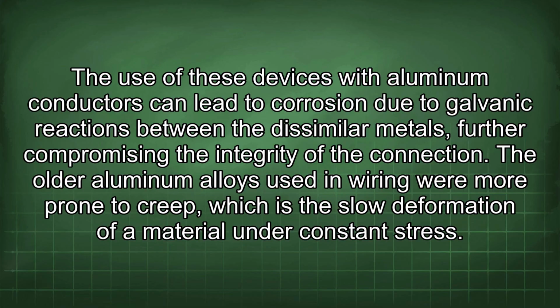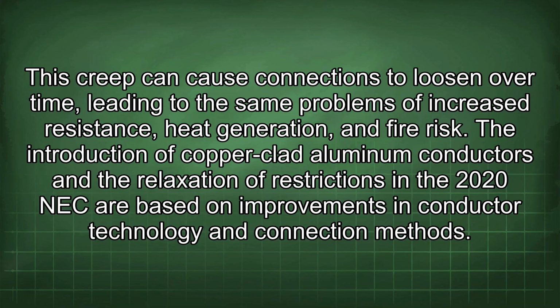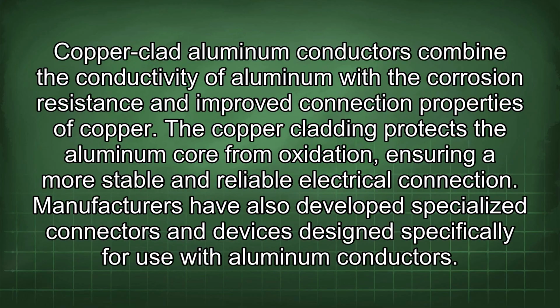The older aluminum alloys used in wiring were more prone to creep, which is the slow deformation of a material under constant stress. This creep can cause connections to loosen over time, leading to the same problems of increased resistance, heat generation, and fire risk. The introduction of copper-clad aluminum conductors and the relaxation of restrictions in the 2020 NEC are based on improvements in conductor technology and connection methods. Copper-clad aluminum conductors combine the conductivity of aluminum with the corrosion resistance and improved connection properties of copper. The copper cladding protects the aluminum core from oxidation, ensuring a more stable and reliable electrical connection.